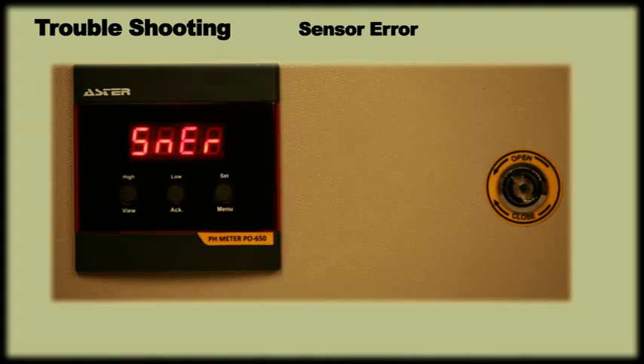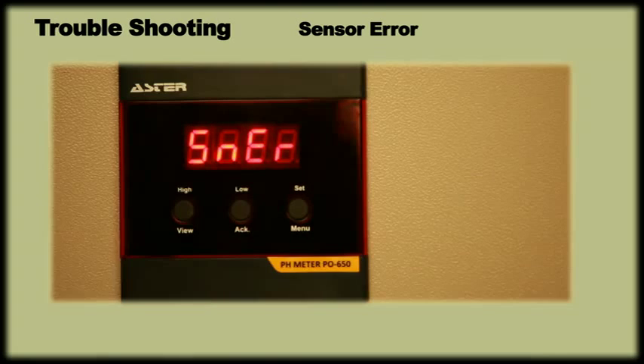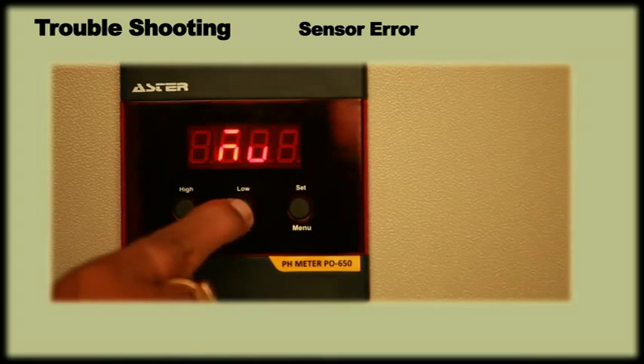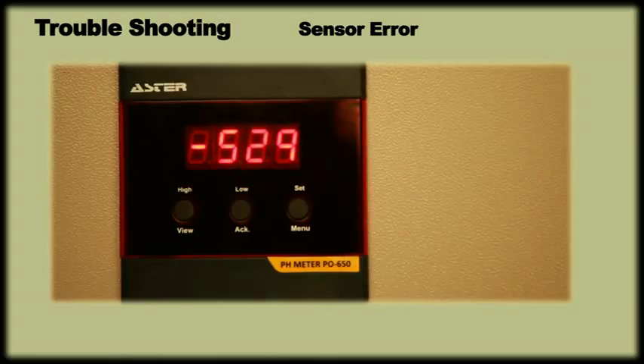If the meter shows sensor error on screen, then press ACK key and check millivolt output of the sensor. If the output is out of range, that is more than 500 or less than -500, you might need to replace the sensor. Contact the nearest service center.